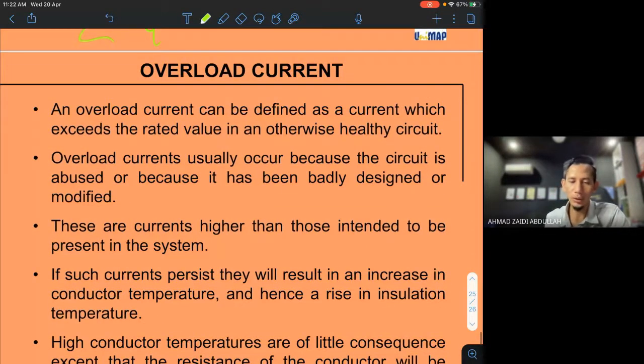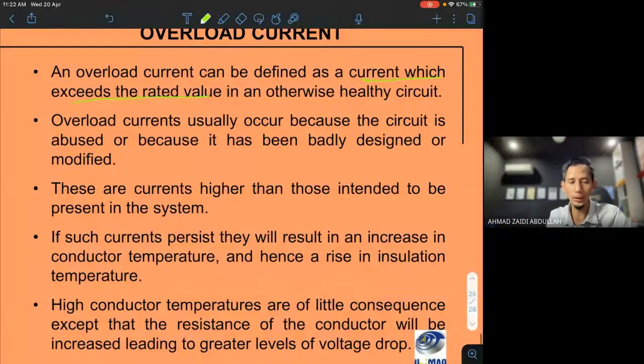Okay, overload can be defined as current which exceeds the rated current, more than the rated. That is the overload. Overload current usually occurs because the circuit is abused or because it has been badly designed or modified. It is based on your design. Let's say the breaker for the socket is only 20 amp, but you put 10 sockets, and the protection for the sockets is just 20 amp.